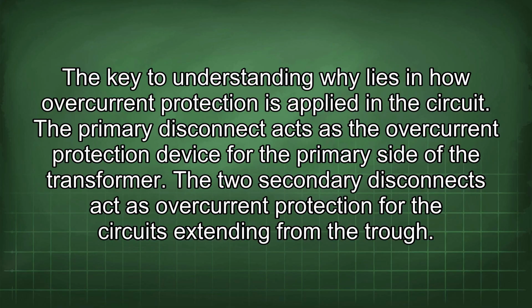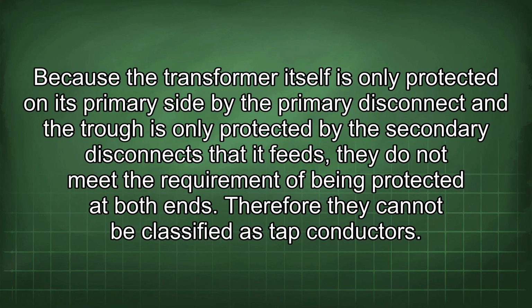The primary disconnect acts as the overcurrent protection device for the primary side of the transformer. The two secondary disconnects act as overcurrent protection for the circuits extending from the trough. Because the transformer itself is only protected on its primary side by the primary disconnect and the trough is only protected by the secondary disconnects that it feeds, they do not meet the requirement of being protected at both ends. Therefore, they cannot be classified as tap conductors.